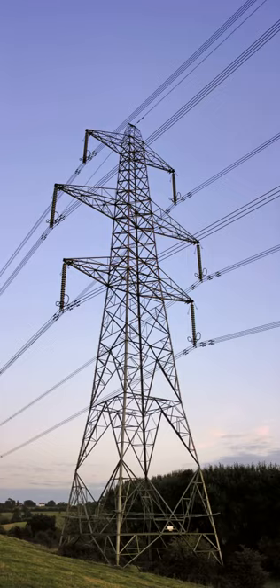it to ground. Towers for high and extra high voltage are usually designed to carry two or more electric circuits, with very rare exceptions, only one circuit for 500 kV and higher. If a line is constructed using towers designed to carry several circuits, it is not necessary to install all the circuits at the time of construction.